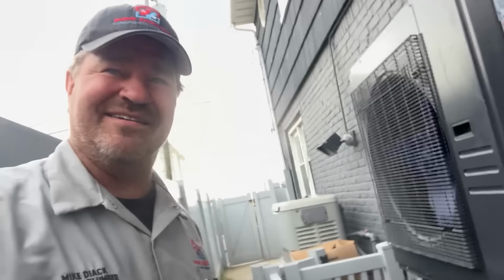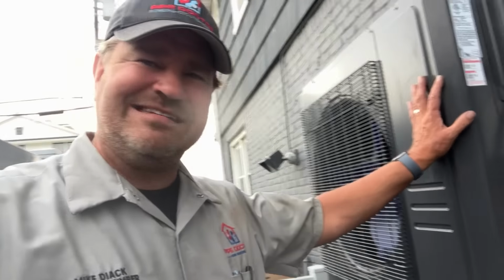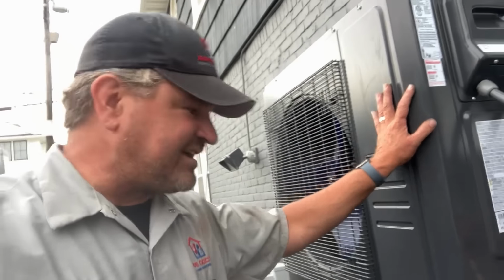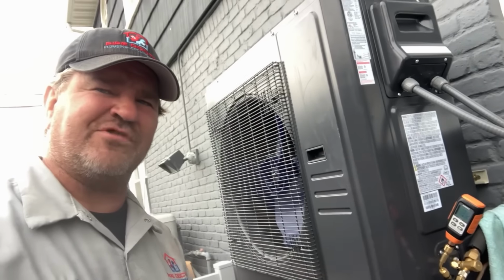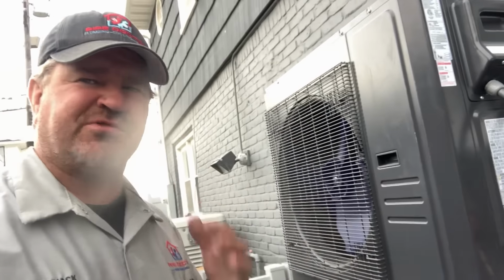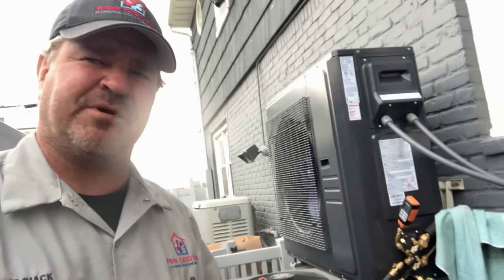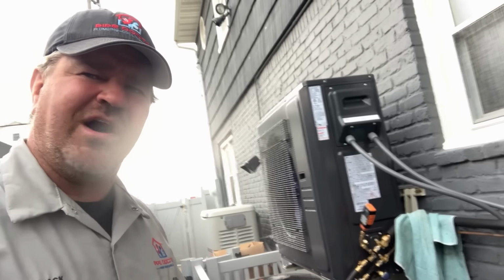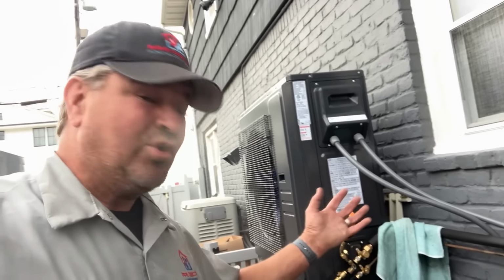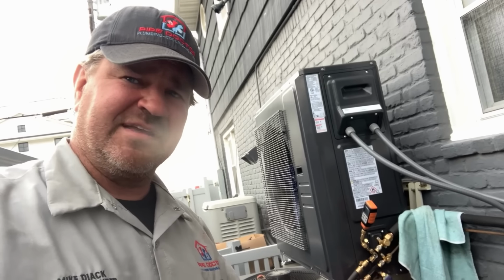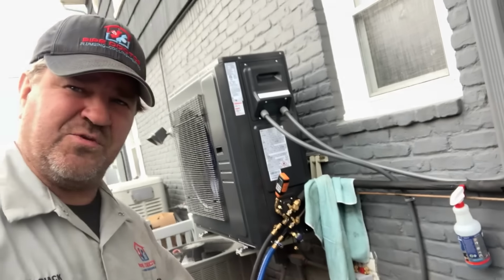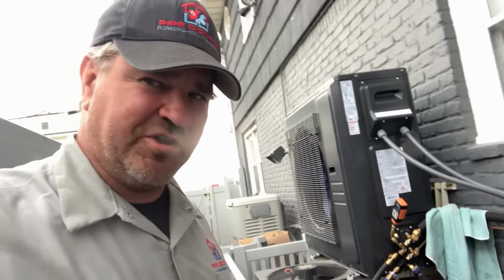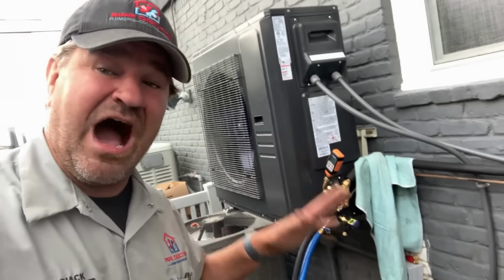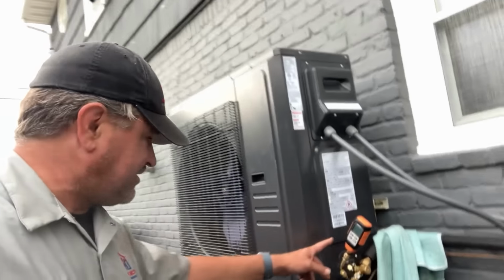Air. Air is just as bad. Air is what we call a non-condensable gas. It doesn't belong in the refrigeration circuit. It raises head pressure, increases compressor workload, reduces efficiency, and makes the entire system consume more electricity while delivering less cooling, or heating if you have a heat pump. And that's why we just don't hook up a vacuum pump for 15 minutes and call it a day. This could take hours.